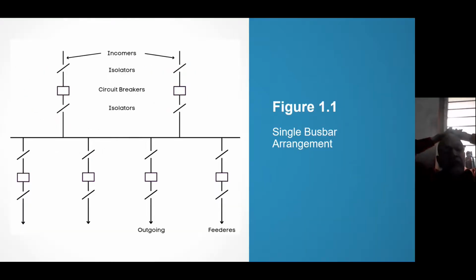You see, this substation is 50 MVA or 100 MVA. At a time, abruptly 100 MVA is lost. That may lead to power system instability. Instability means generators will slip poles. Pole slipping will occur, and generators will start getting disconnected from the bus. And if all generators get disconnected from the bus, it is known as cascaded tripping. To resume power from cascaded tripping may take 3-4 hours to a maximum of 7 hours, because a thermal power plant cannot be started within a minute.